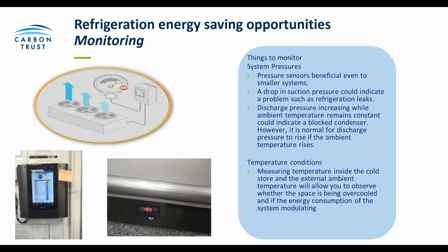And in terms of temperature, you can clearly see where you can make sort of granular changes. If you've got granular data that tells you the different cabinets' temperatures, you can see that different cabinets may need different kinds of changes made to them. An example we've worked with was a small supermarket that had a clear display of temperature on all of their cabinet units. They were able to see which ones were defrosting when they shouldn't be, and they were able to make individual improvements to each of those cabinets. So making sure you have the granularity of information available to you can be of real benefit.